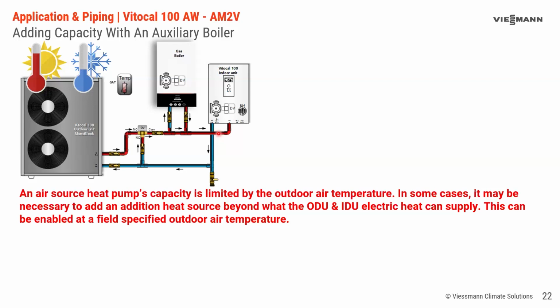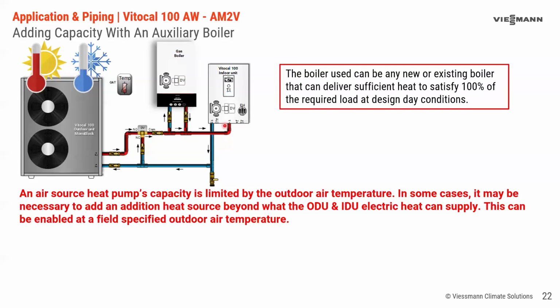We can say we may need a backup boiler. So you see the backup boiler, how we've piped it here. We've piped it in closely spaced tees in line with the line that comes from the outdoor unit. So this is how we would be able to supplement the heat. Now, this boiler could be any boiler. It could be a brand new boiler you bought for this. It could be the boiler that's existing in the boiler room and it's already there. You're just going to repurpose it, repipe it so that it's used as the backup. And there is a dry contact in the indoor unit to enable this boiler.